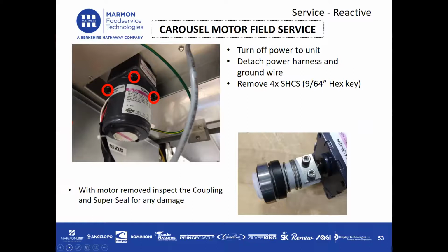If you had to replace the carousel motor out in the field, you want to turn off the power to the unit, detach the power harness and ground wire, and then remove the screws that secure this motor to the drip tray from underneath. Once you have the motor removed, it all comes down as one assembly. At this moment, you would also want to inspect the coupling and the super seal for any damages.